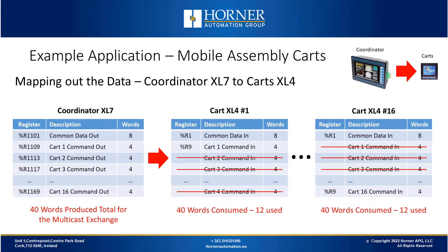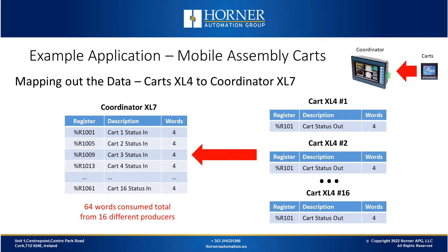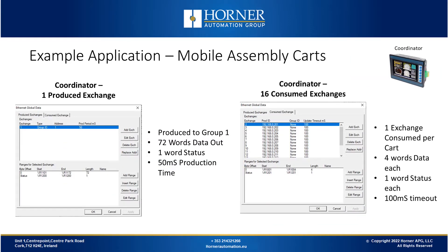Let's map out the data and see what that looks like. Starting with our coordinator XL7, the command data is sent out to all the carts. Every cart receives that message of data every 100 milliseconds and using some logic it will only use the data it cares about. Every cart will have some common command data stored in register 1 for example, and then another bank of registers with individual commands specifically targeted for that particular cart. For data going in the other direction, every cart is sending status to the network as a single exchange. The coordinator XL7 is receiving that status information through 16 different exchanges and mapping that information.